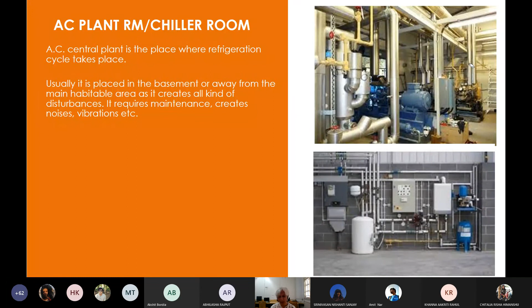So compressors, condensers, chillers, or evaporators are placed in the basement. Requires extensive maintenance and hence should be easily accessible, creates high vibration, hence structural components to be taken care of. Pumps, okay, there are pumps working there, the compression is working there, so it creates vibration. So you need to give me isolator pads, concrete isolator pads. You will have to provide that to take care of the vibrations.